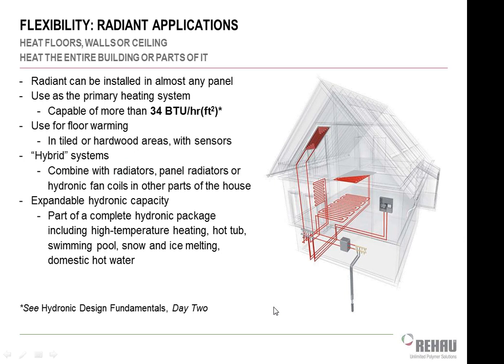Once you do decide to go to a radiant floor system and you purchase a boiler, then it makes sense to use that boiler to heat lots of other stuff in your house. So like I said, you might have radiators in some older parts of the house. Maybe you put an addition on, put floor tubing in the new addition, but it's easier to go back and retrofit radiators in the old area as opposed to floor tubing.